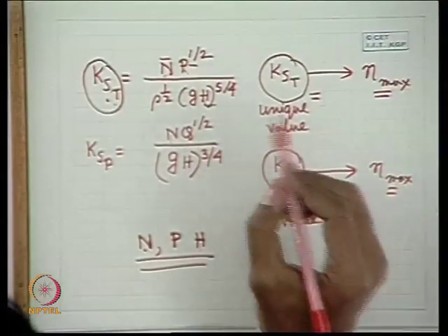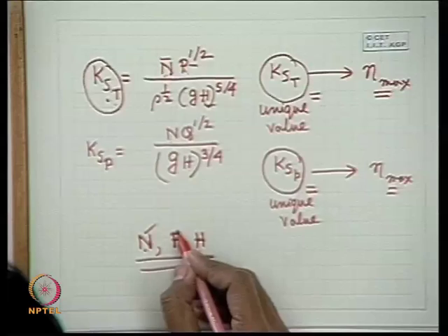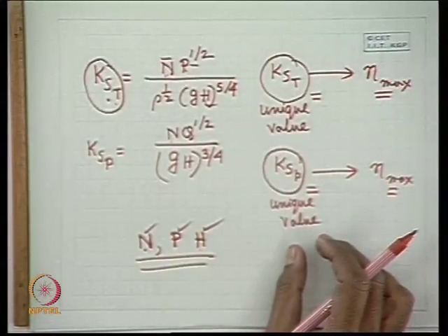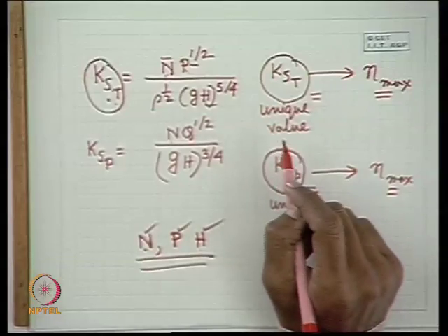Now we see this value of KST as obtained from N, P and H, which are specified as the performance parameters, the output parameters that have to be met. We will see which class of turbines gives the maximum efficiency at that value of KST. Then we will select that class of turbine, because it will give the maximum efficiency for this operation.